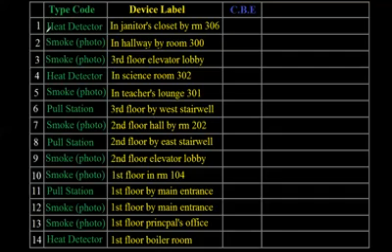Like I can have a smoke detector. The smoke photo is a common type code for the Notifier panels, but I could have a smoke detector that doesn't cause an alarm when it's activated. It causes a supervisory, so there's a different type code for that. I could have a fixed temp heat detector or a high temp heat detector, which would be like maybe 195 degrees or whatever. But anyway, that's basically what the panel really cares about.